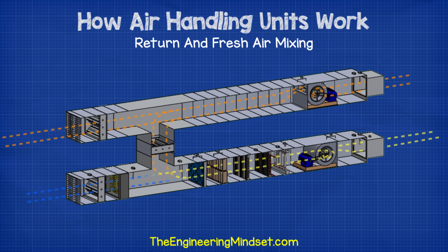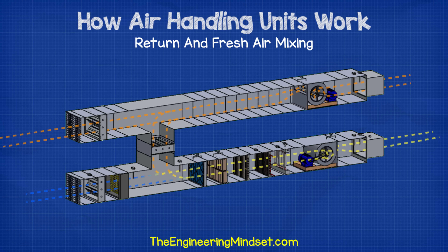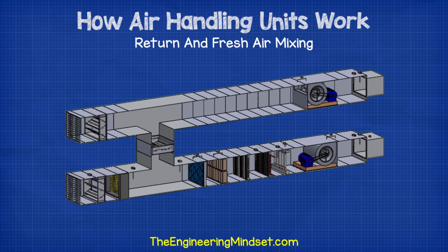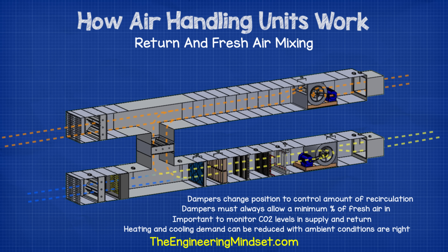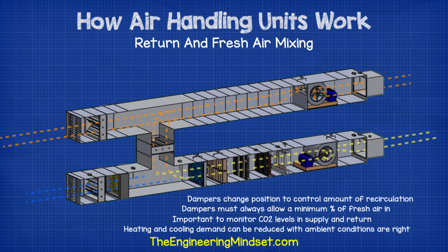Another very common version is to have a duct sit between the exhaust and the fresh air intake. This allows some of the exhaust air to be recirculated back into the fresh air intake to offset the heating and cooling demand. An additional damper sits within the connecting duct to control how much air can be recirculated. This is safe and healthy to do, but you need to ensure the exhaust air has a low CO2 count, so we need CO2 sensors to monitor that. If the CO2 level is too high then the air can't be reused — the mixing damper will close and all the return air will be rejected from the building. When in recirculation mode, the main inlet and outlet dampers will not fully close because we still need a minimum amount of fresh air to enter the building. We can use this in winter if the return air is warmer than the outside air, and also in summer if the return air is cooler than the outside air, respected to the supply set point temperature. We'll also need temperature sensors at the intake, return, and just after the mixing region. Some buildings require 100% fresh air so this strategy can't be used everywhere — local laws and regulations will dictate this.